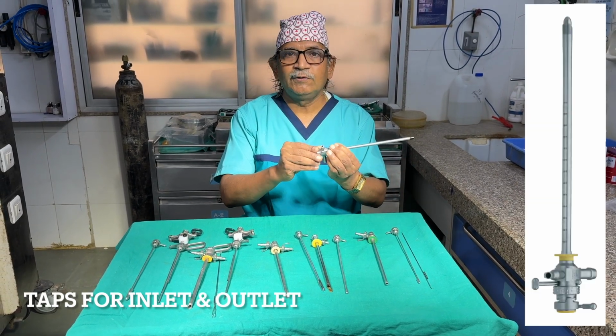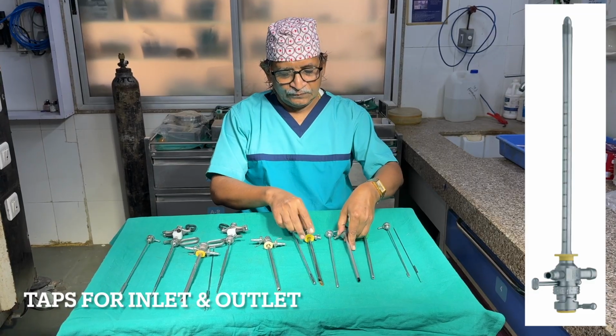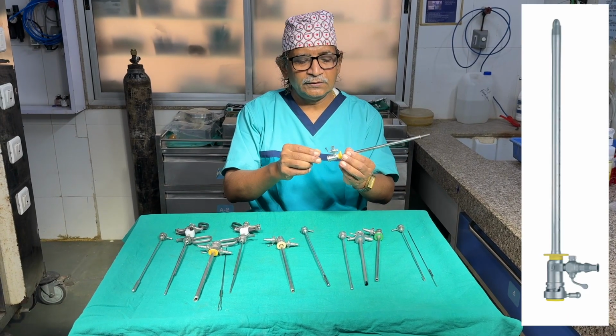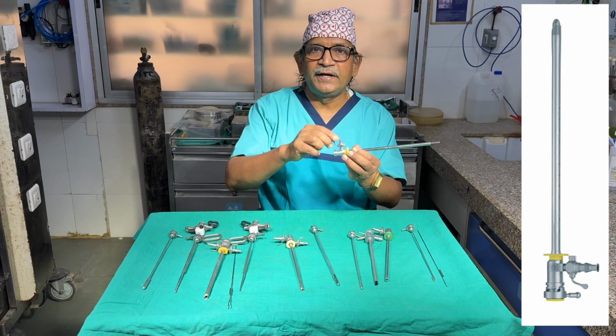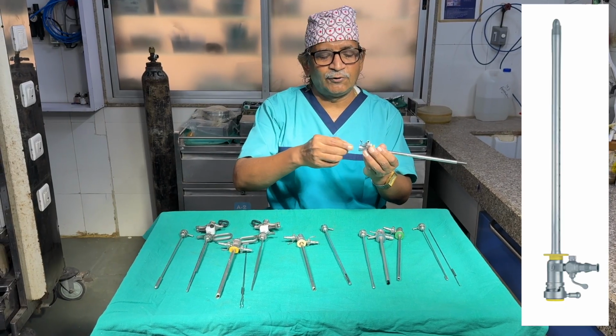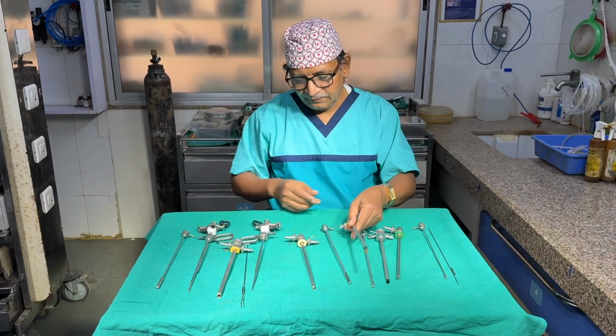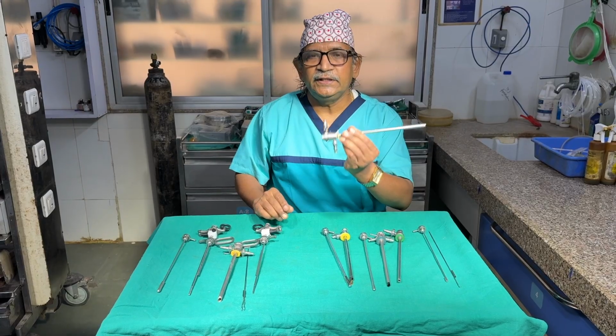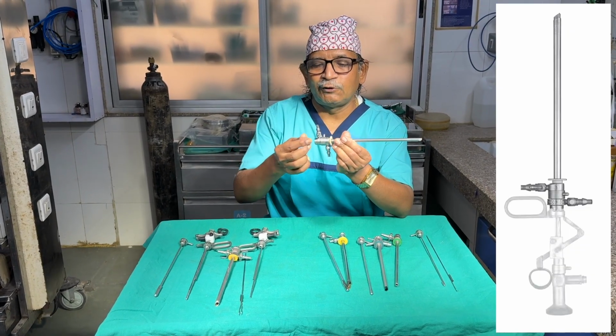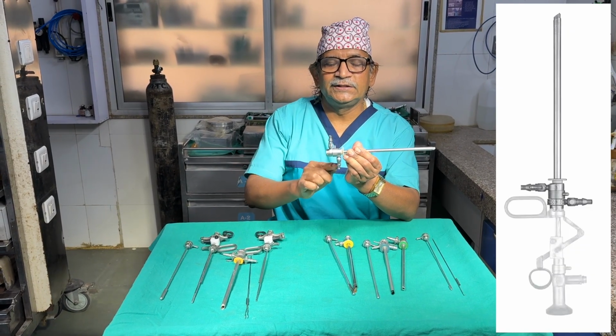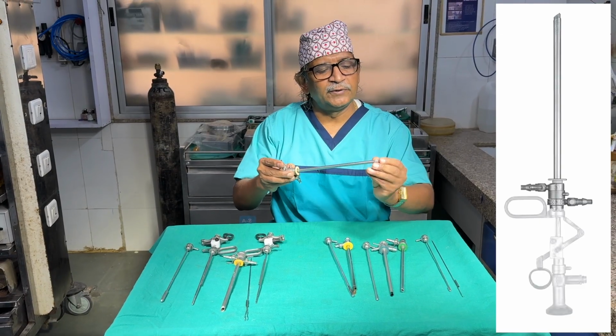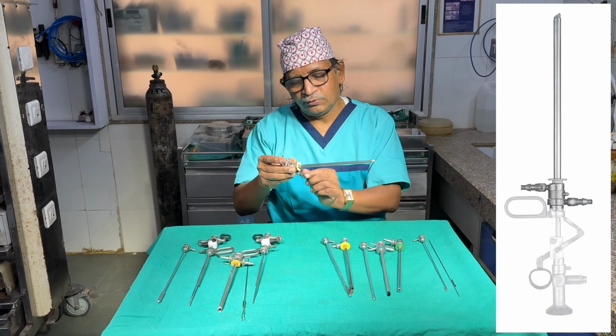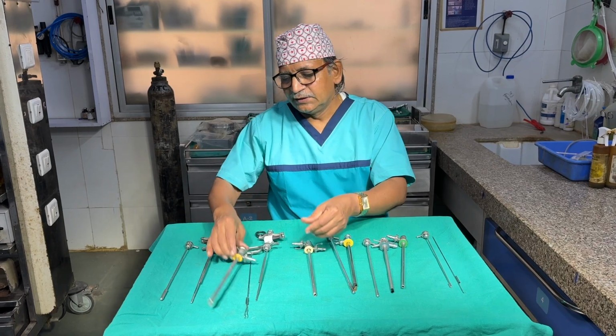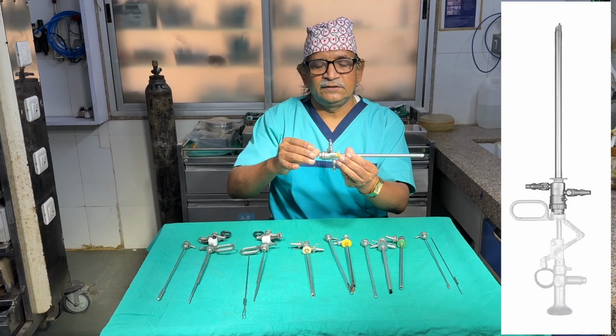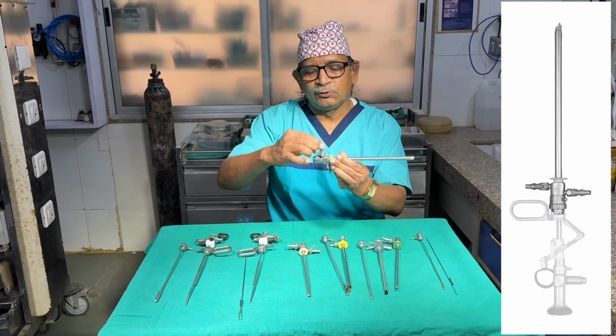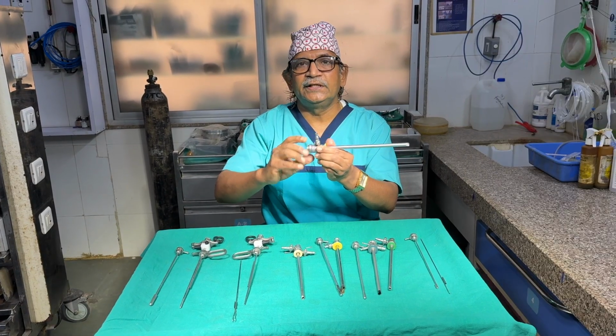This is the central valve. This is the standard old intermittent irrigation sheath. Only one tap which acts as an inlet, and for outlet you have to remove the working element. This is the continuous irrigation non-rotatable sheath. This is the water inlet, this is the water outlet. The water comes in from here, and then from here the water goes out and drains through this sheath. This is the continuous irrigation resectoscope sheath but a rotatable one. So this you can rotate the inner sheath.